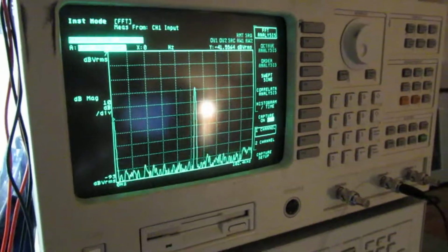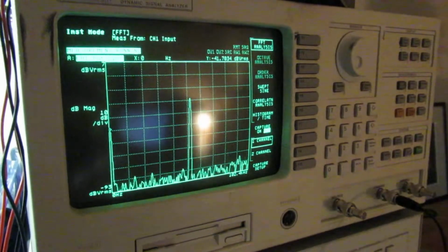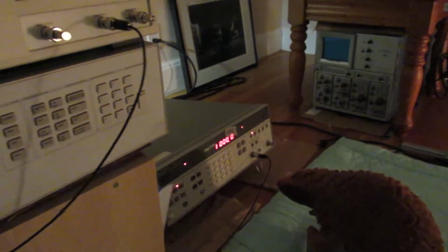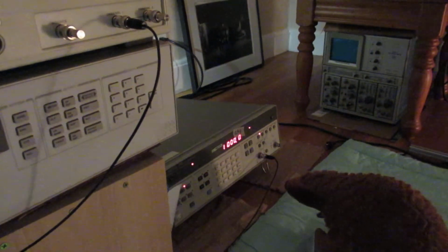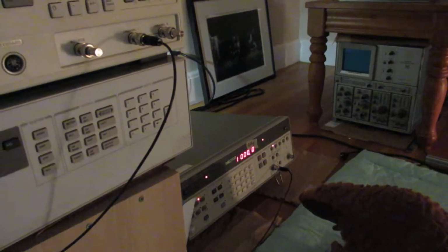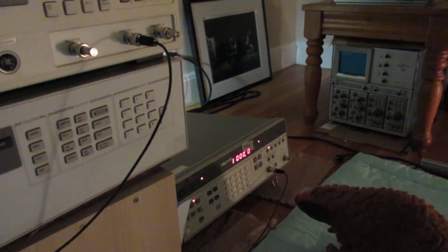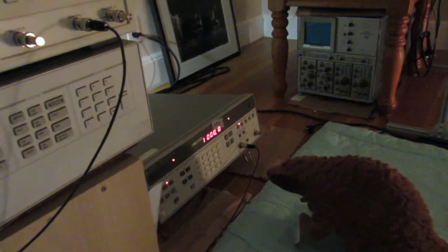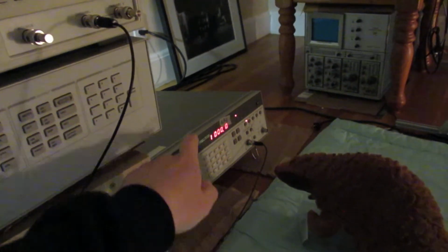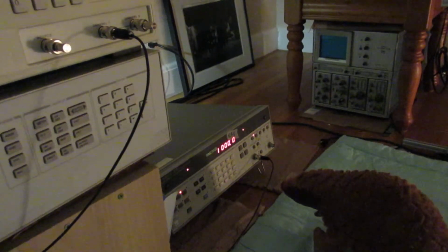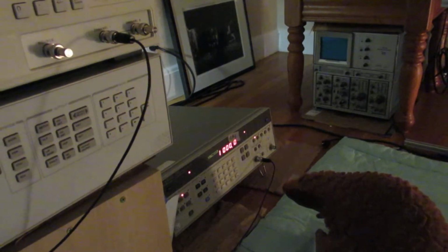Yeah. So I really wanted a function generator, and I got kind of hooked on having one of these, or access to one of these at work. Massive overkill for what I am doing at home, but the beauty of having it is that it is the calibration instrument. You are supposed to calibrate one of these and one of these, and actually other than buying an outright, full calibrator, that is one of the tools you use to verify an HP 3458. So, it's pretty awesome.